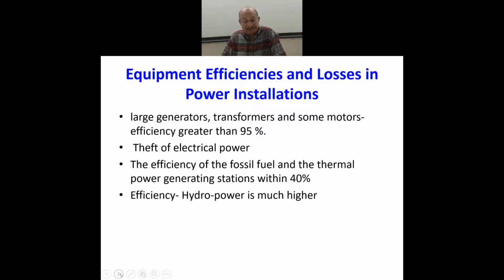If we had increased the current instead of voltage, you can imagine I squared R loss is the real power loss. So the efficiency of the transmission lines would have gone down like anything. So it is not desirable to increase the current, but if we increase the voltage, we can increase the power handling capability of any three-phase system.